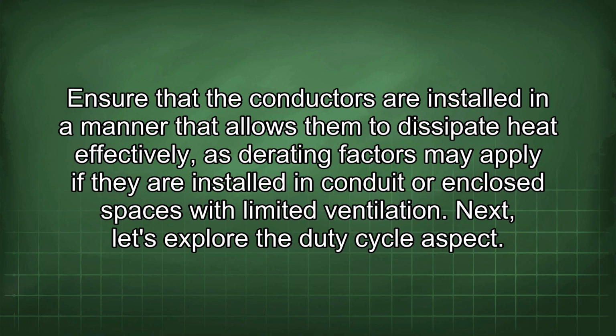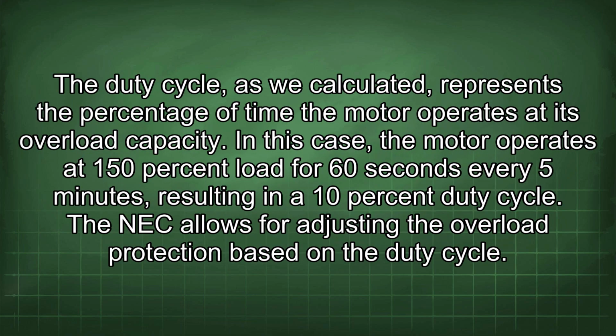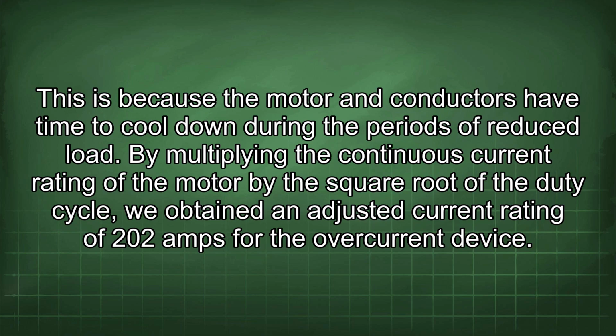Next, let's explore the duty cycle aspect. The duty cycle, as we calculated, represents the percentage of time the motor operates at its overload capacity. In this case, the motor operates at 150% load for 60 seconds every 5 minutes, resulting in a 10% duty cycle. The NEC allows for adjusting the overload protection based on the duty cycle. This is because the motor and conductors have time to cool down during the periods of reduced load. By multiplying the continuous current rating of the motor by the square root of the duty cycle, we obtained an adjusted current rating of 202 amps for the overcurrent device.